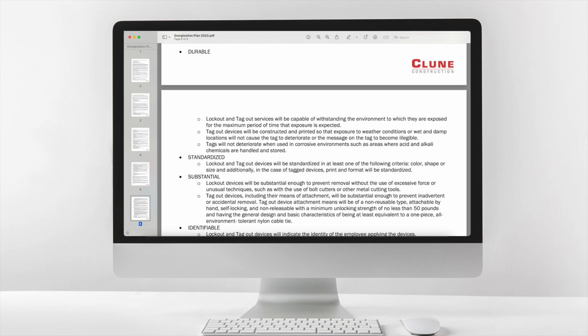Durable. Lockout and tagout devices will be capable of withstanding the environment to which they are exposed for the maximum period of time that exposure is expected. Tagout devices will be constructed and printed so that exposure to weather conditions or wet and damp locations will not cause the tag to deteriorate or the message on the tag to become illegible. Tags will not deteriorate when used in corrosive environments such as areas where acid and alkali chemicals are handled and stored. Standardized. Lockout and tagout devices will be standardized in at least one of the following criteria: color, shape or size, and additionally, in the case of tagged devices, print and format will be standardized.